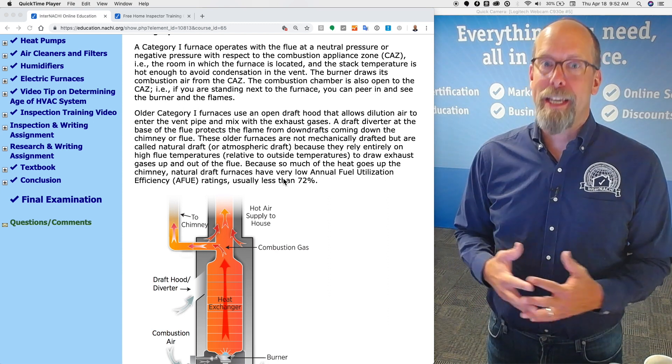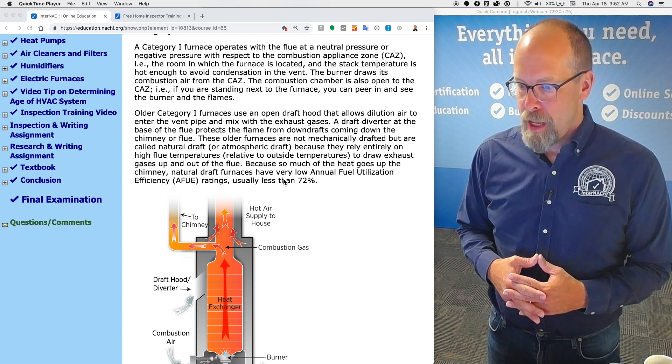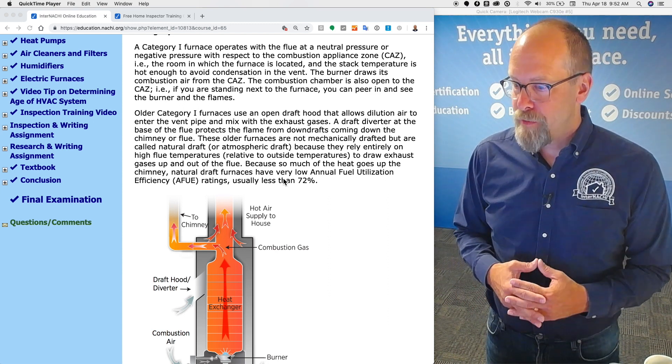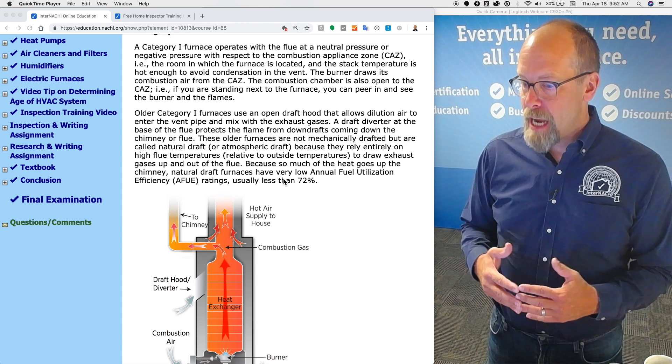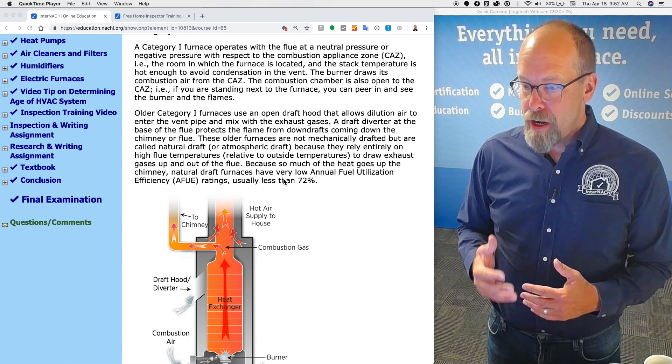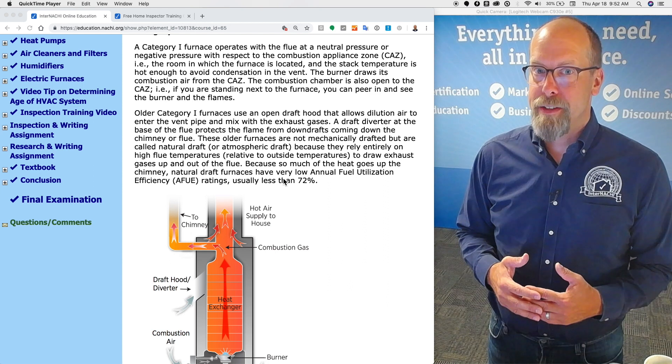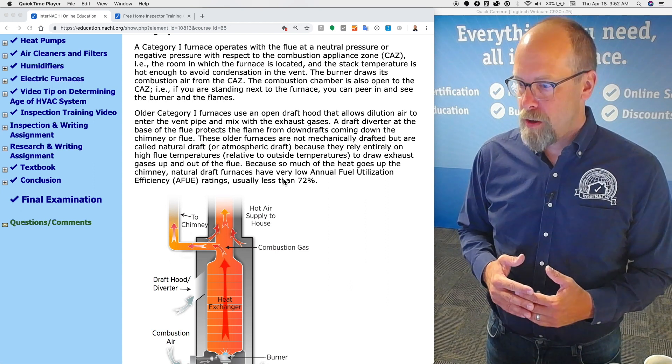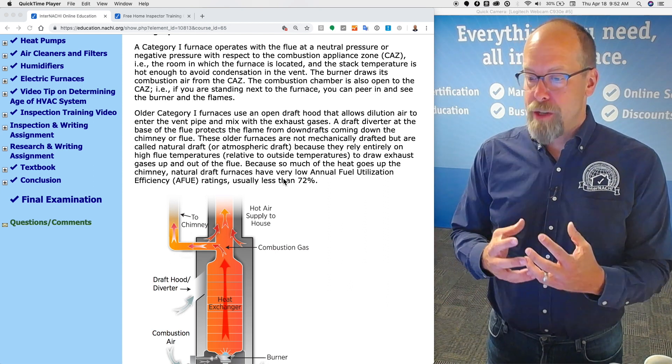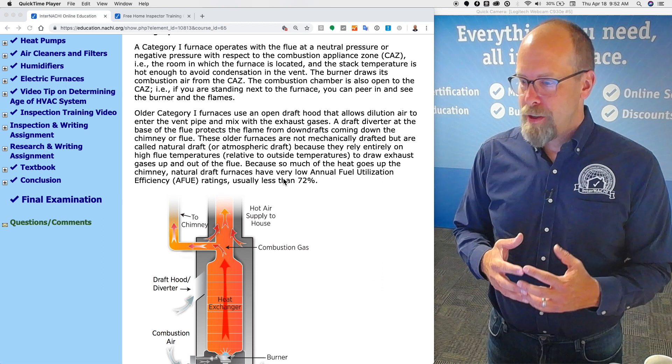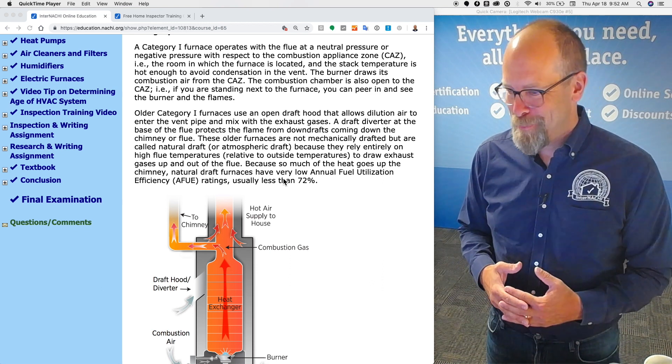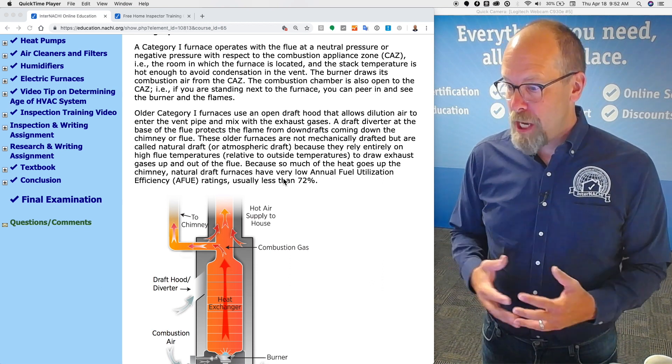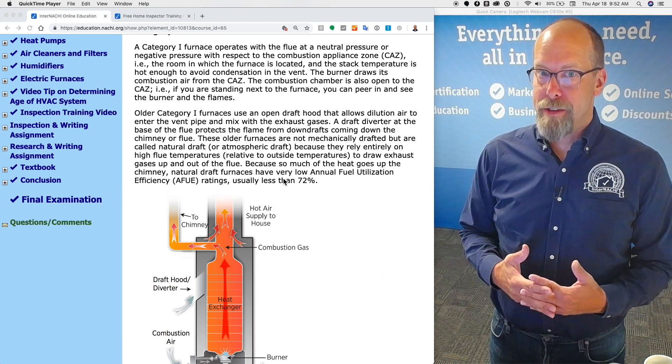That's the room in which the furnace is located. The stack temperature is hot enough to avoid condensate in the vent in a category one. The burner draws its combustion air from the CAZ, the combustion appliance zone. The combustion chamber is also open to the CAZ. For example, if you're standing next to the furnace, you should be able to look in and see the burner and the flames.